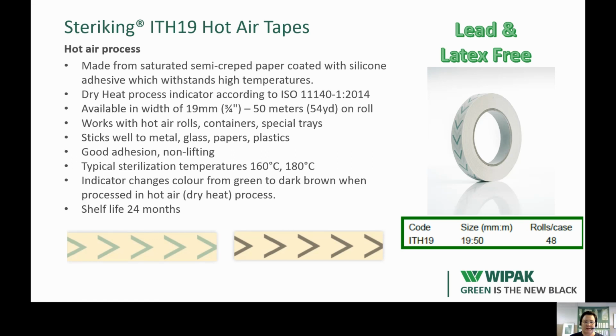And the indicator is again according to this chemical indicator standard. And this tape is available in one width of 19 millimeters and 50 meters on a roll. And this can be used for closing the hot air rolls or pouches made from nylon, then containers, special trays, because it sticks very well to metal and also glass, but then also paper and all different types of plastics that are sterilized in dry hot air sterilization.